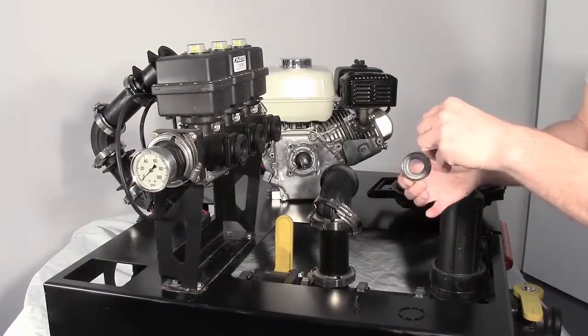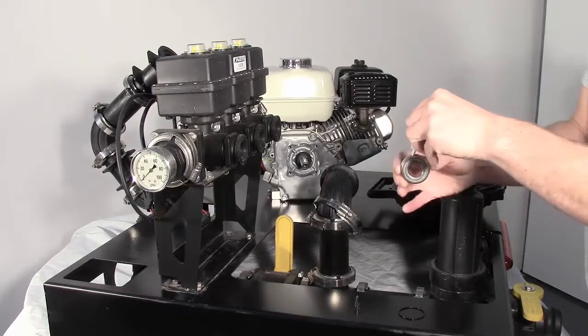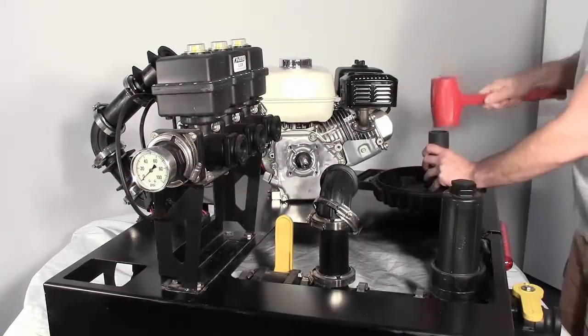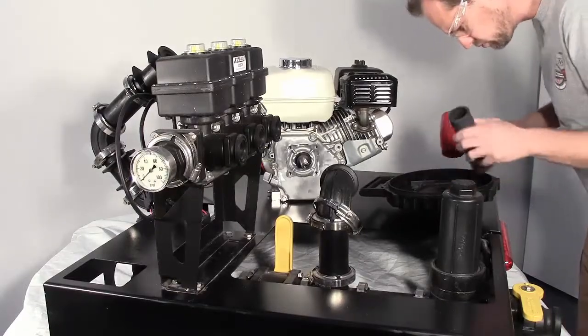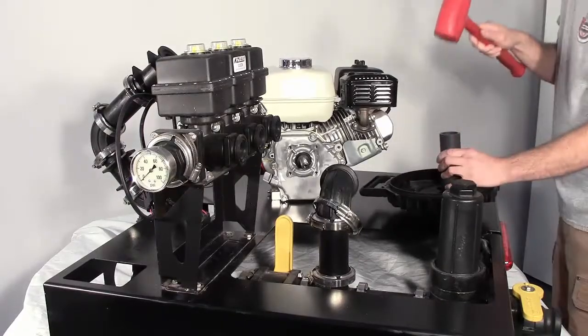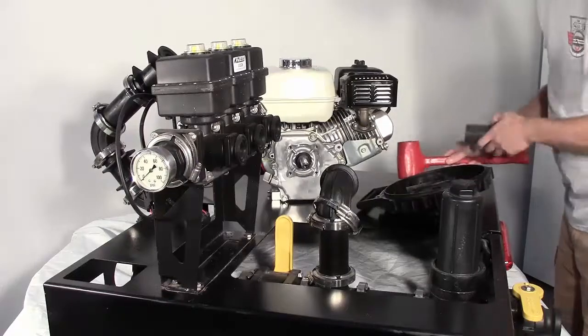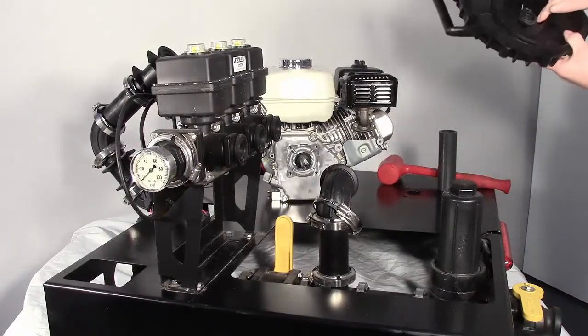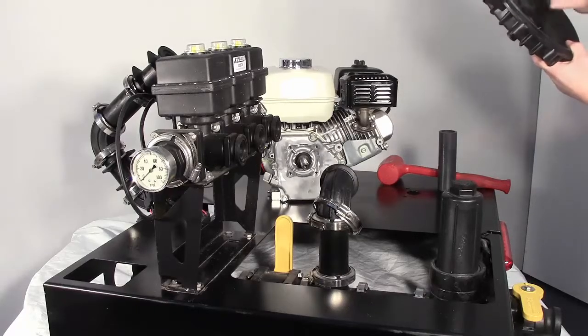Apply dielectric grease to the seal and then slide on the black O-ring. Install the seal assembly into the rear bracket using a tool such as a one and a half inch pipe nipple or arbor press to give even pressure on the metal flange of the seal housing during installation.